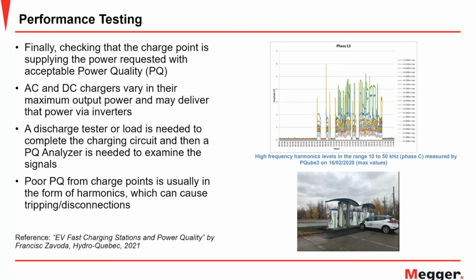Anecdotally, and it is just an anecdote, a good friend of mine has a Tesla. He charges it at home, and every once in a while his fuse box in the house trips while he's charging overnight. And he asked Tesla about this, and they said, yeah, it's a known issue with that older generation of the Tesla. And when we looked at it ourselves and took some power quality readings in there, we saw that the inverter is taking the AC power coming out of his wall and turning it into DC to charge the batteries. That can sometimes produce some high frequency harmonics, which, if they rise to a high enough level, cause the tripping.